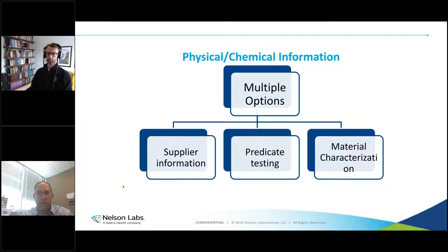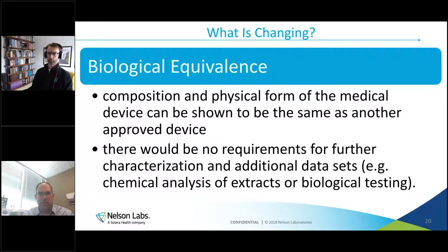Okay, so the other thing we're adding is we're trying to get more into what we call biological equivalence. And this goes back to that predicate concept, where if your composition, physical form, and processes are the same as another approved medical device, then why are we requiring further testing and characterization, right? So if we're able to demonstrate similarities between a device already on the market and those things we talked about, those inputs, the materials, the physical form, residuals, things like that, then we should be able to get away from doing further characterization and data sets like testing. Next slide, please. So that will be in the new standards, some more guidance on that.